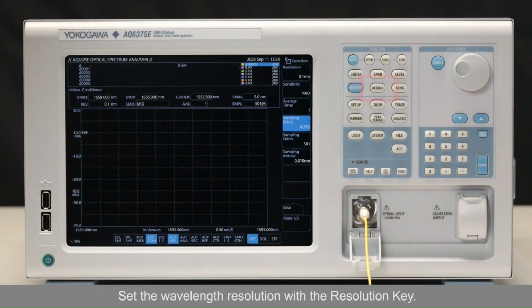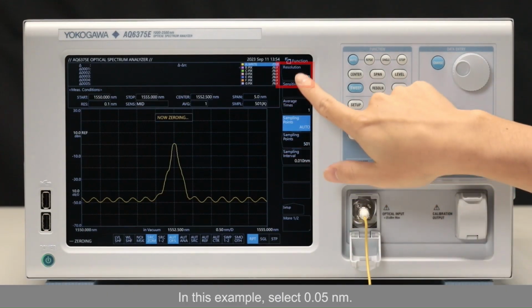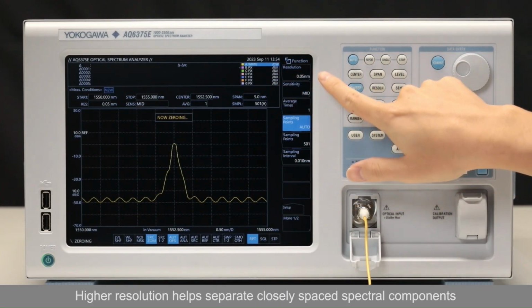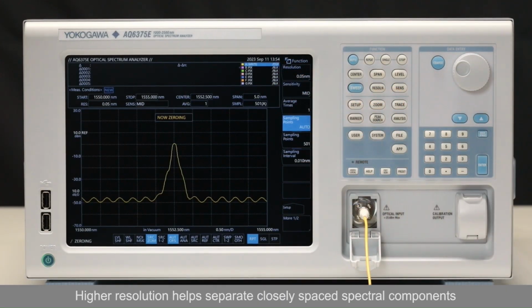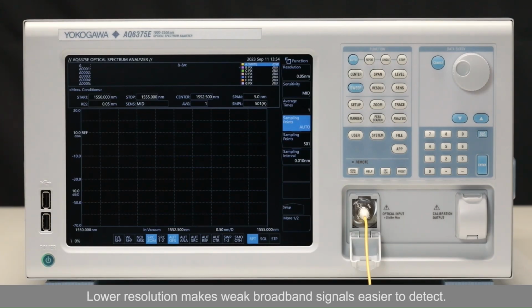Set the wavelength resolution with the resolution button. In this example, select 0.05 nanometers. Higher resolution helps separate closely spaced spectral components. Lower resolution makes weak broadband signals easier to detect.